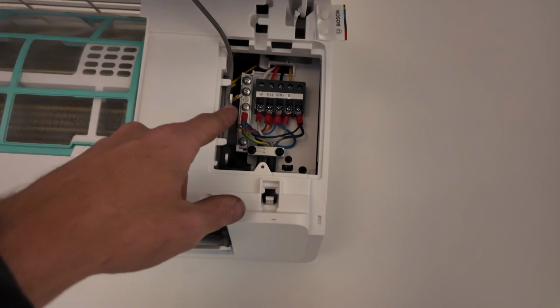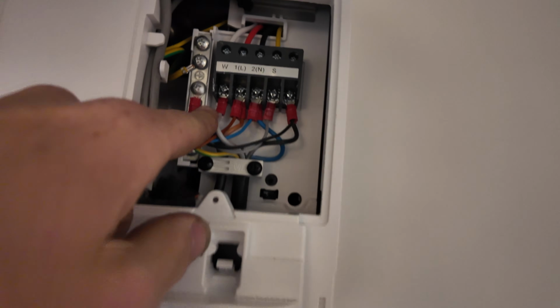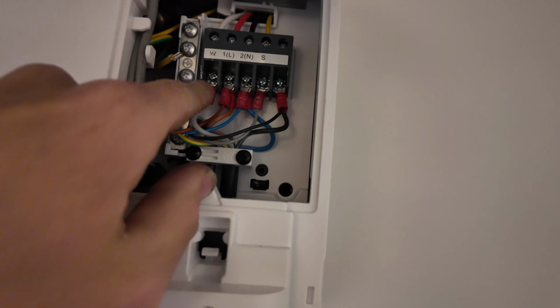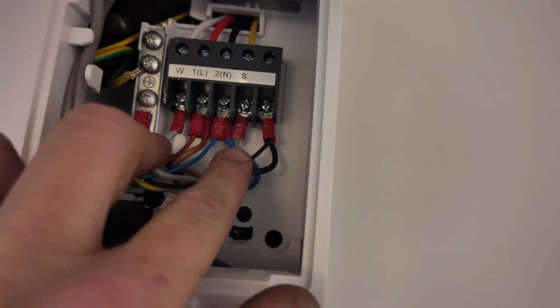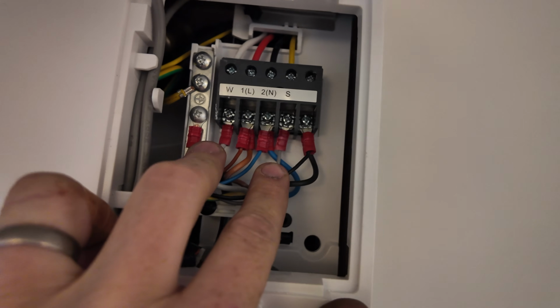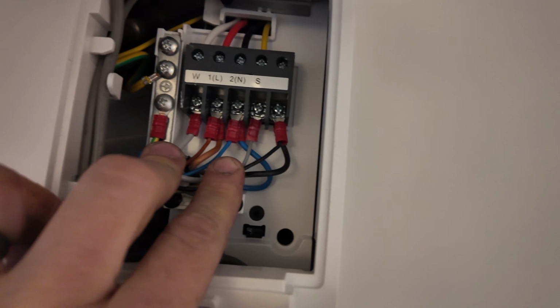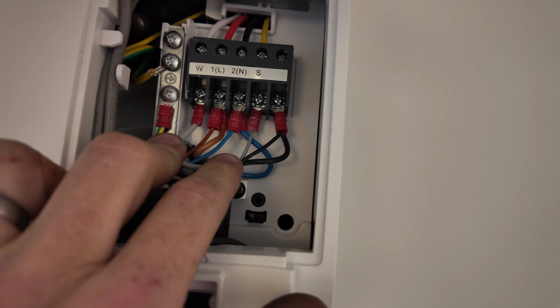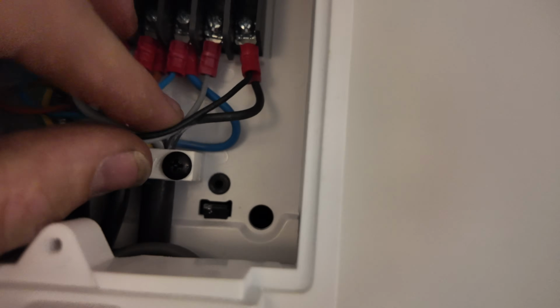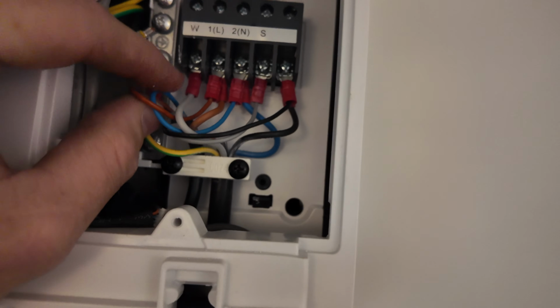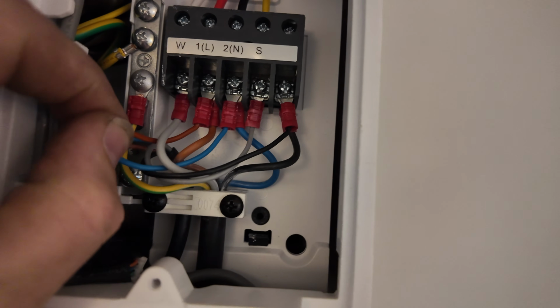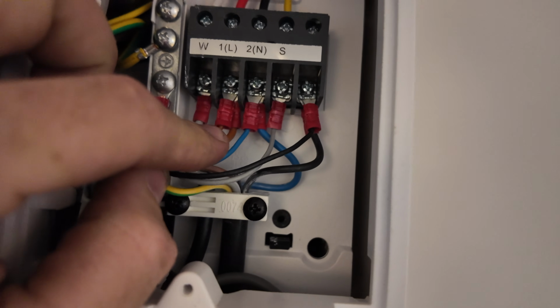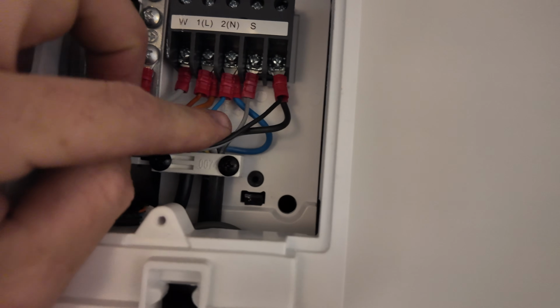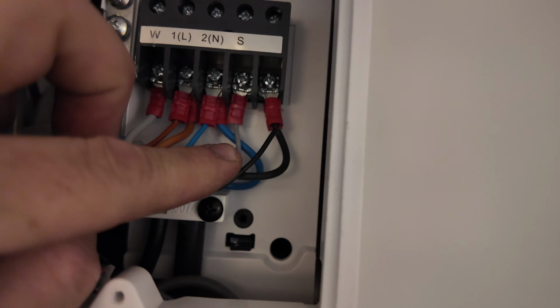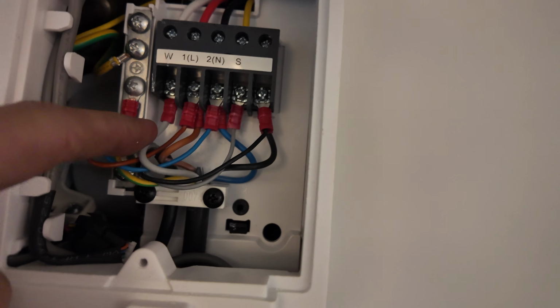So I'm just going to explain the wiring. You can see it's all wired up on ferrules - we put all them in. So you've got W and S in your two switches. Whatever you wired indoor, wire it the same as whatever you wired outdoor. The smaller cables here are off the condensate pump - it's got live and neutral. Live goes into live, connected to your outdoor unit, neutral's neutral. You've got one of your switches here which is S, and the other switch here which is W.